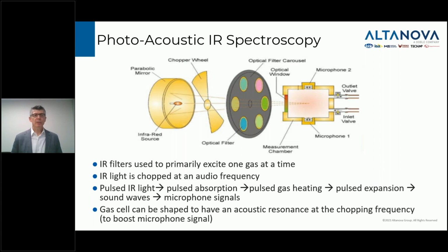The light then passes through an optical filter. Typically, there are a collection of different optical filters that can be put into position to measure the different gases one at a time. So what ends up being shined into the gas sample is a chopped, filtered beam that's designed to excite one gas at a time from the family of possible gases that could be in the sample.